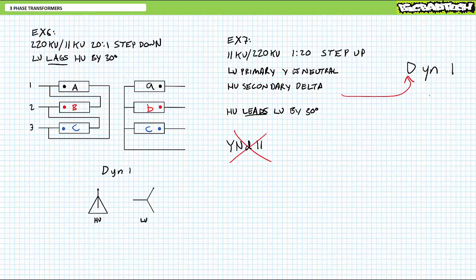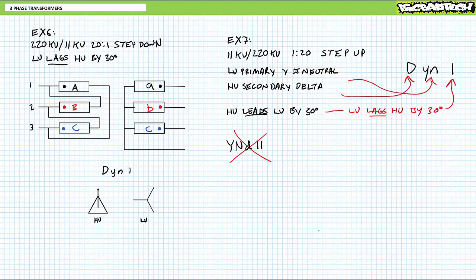If we were to use standard nomenclature, which we are going to, we need to express the delta-configured high-voltage secondary output side first as capital D. The Y-configured low-voltage primary input side with the neutral second using lowercase yn, and then reference low-voltage input with respect to high-voltage output, not the other way around. If high-voltage output leads low-voltage input by 30 degrees, this is the same thing as saying low-voltage input lags high-voltage output by 30 degrees. We're clearly dealing with a 1 o'clock transformer. Thus, this 1 to 20 step-up transformer is also a DYN1.